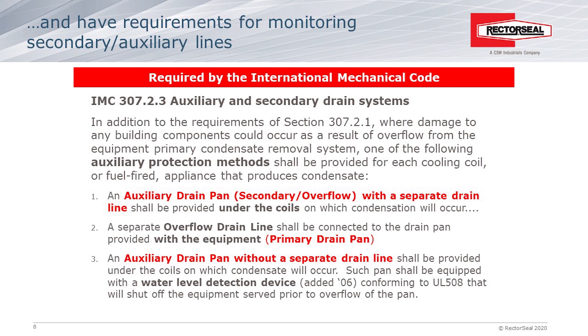Method three uses a water level detection device — usually a float switch or electronic sensor — that must conform to the requirements of UL 508, located in an auxiliary drain pan. These detector devices will shut down the equipment before the pan overflows, and there is no requirement for a separate drain line in this method. Method four also uses a water level detection device, but located in the drain line from the primary drain pan or the overflow line from the primary drain pan, rather than the secondary drain pan as in method three.